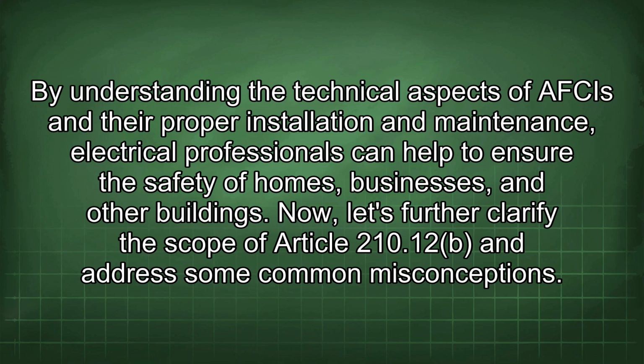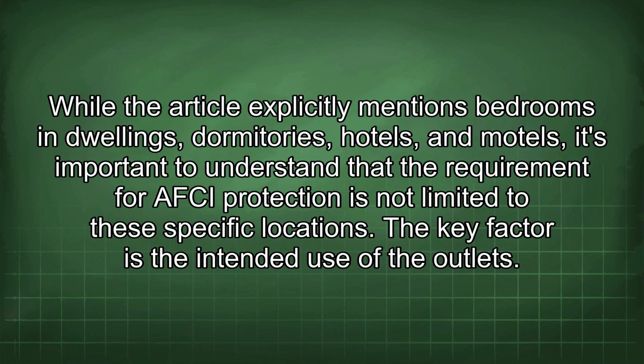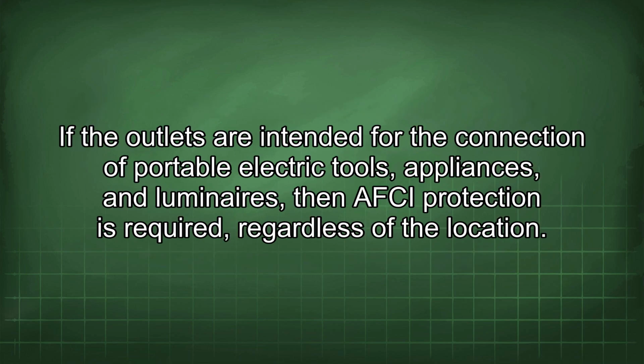Now, let's further clarify the scope of Article 210.12 and address some common misconceptions. While the article explicitly mentions bedrooms in dwellings, dormitories, hotels, and motels, it's important to understand that the requirement for AFCI protection is not limited to these specific locations. The key factor is the intended use of the outlets.